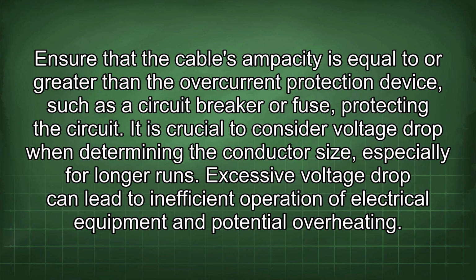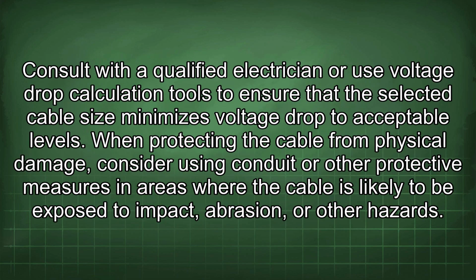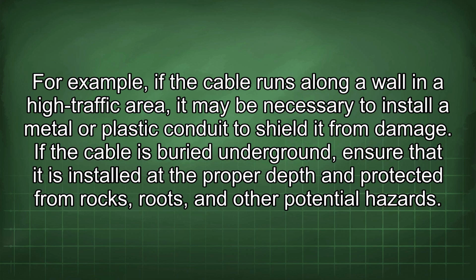It is crucial to consider voltage drop when determining the conductor size, especially for longer runs. Excessive voltage drop can lead to inefficient operation of electrical equipment and potential overheating. Consult with a qualified electrician or use voltage drop calculation tools to ensure that the selected cable size minimizes voltage drop to acceptable levels. When protecting the cable from physical damage, consider using conduit or other protective measures in areas where the cable is likely to be exposed to impact, abrasion, or other hazards. For example, if the cable runs along a wall in a high-traffic area, it may be necessary to install a metal or plastic conduit to shield it from damage.